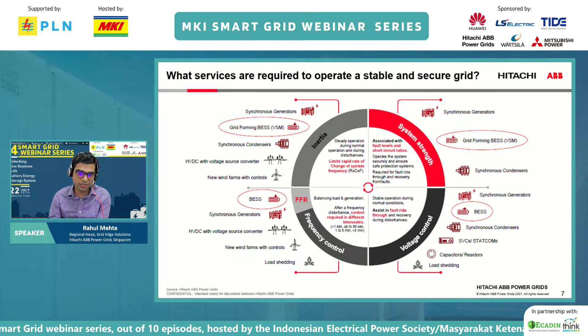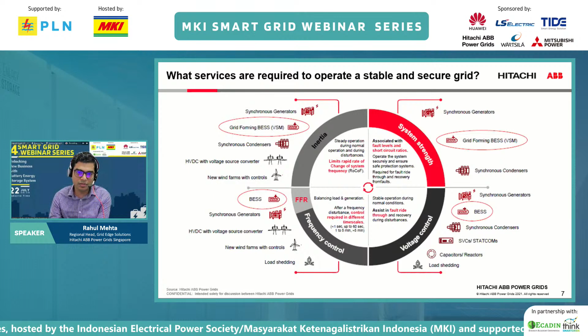This is something that's going to come in the next 4-5 years, where all the countries in this region - Indonesia, Philippines, Thailand, and other places - will see massive adoption of PV. That's where you'll need battery energy storage, specifically grid forming battery energy storage, to provide system strength as well as inertial response. The functions below, frequency control and voltage control, are your secondary response - your second line of defense, supporting the grid by responding to any changes in frequency and voltage as the batteries charge and discharge accordingly.